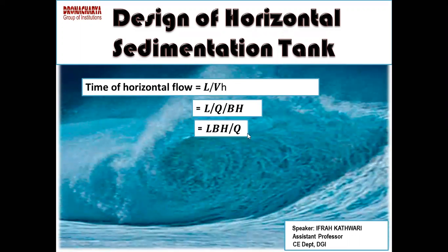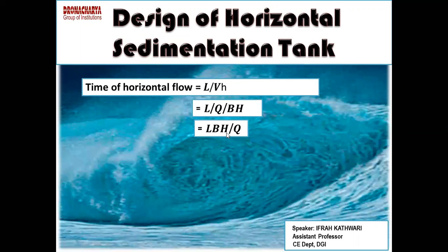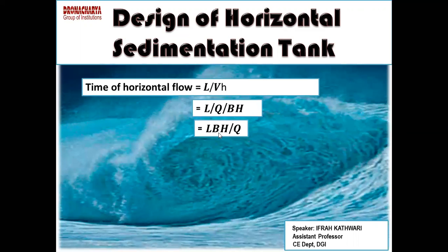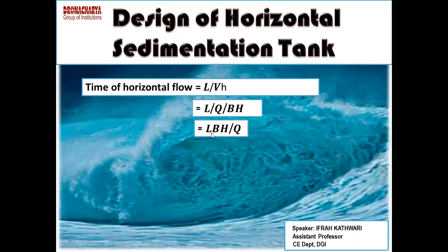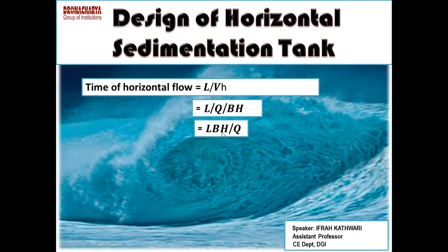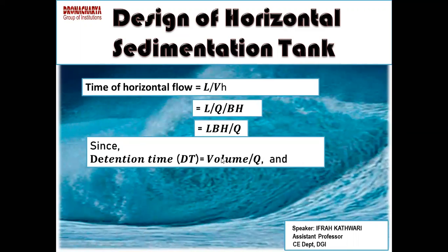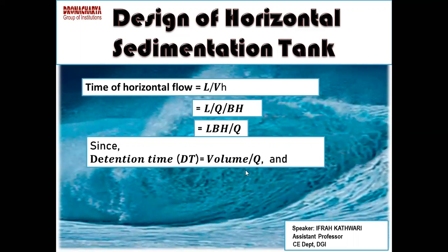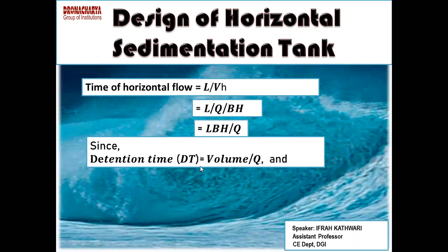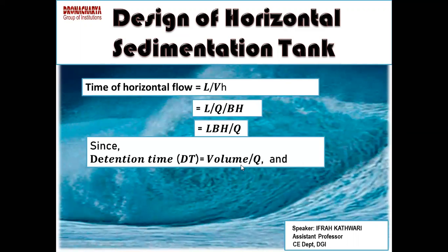So the time of horizontal flow will be equal to LBH upon Q, length into breadth into height upon Q. LBH is the volume, volume upon discharge. So talking about the detention time, the detention time is equal to volume upon the discharge. DT, detention time, is volume upon discharge, or we can say capacity of the sedimentation tank upon the discharge.